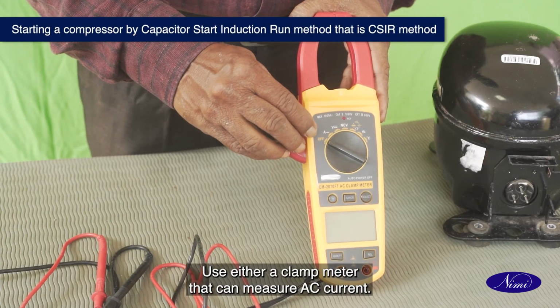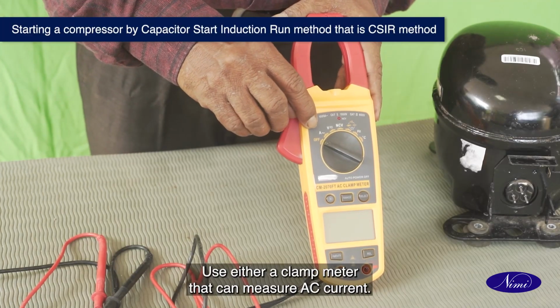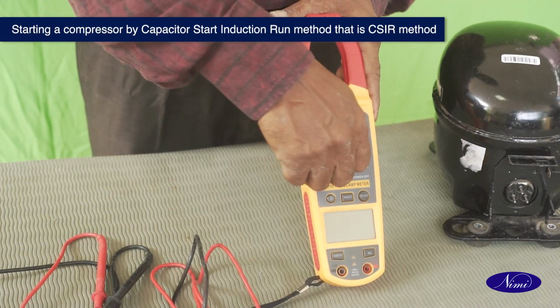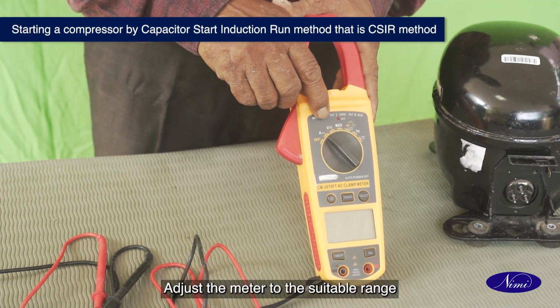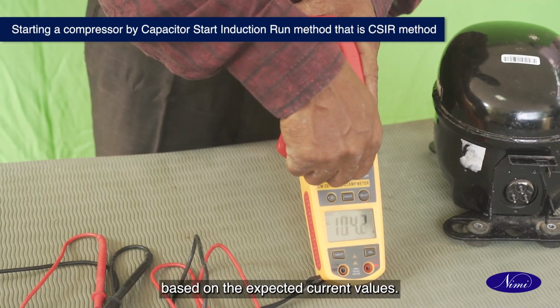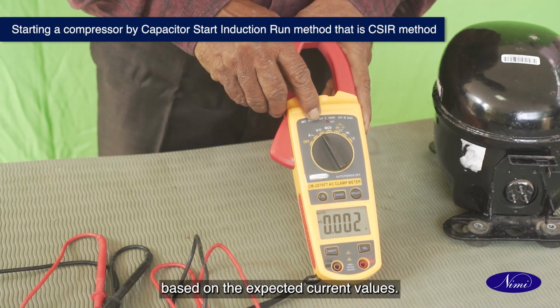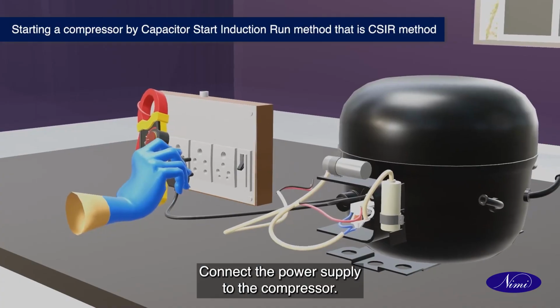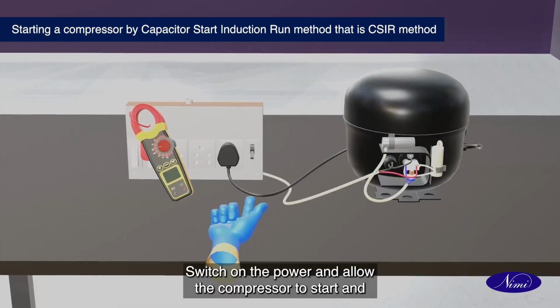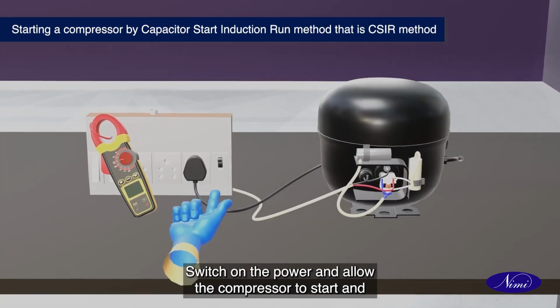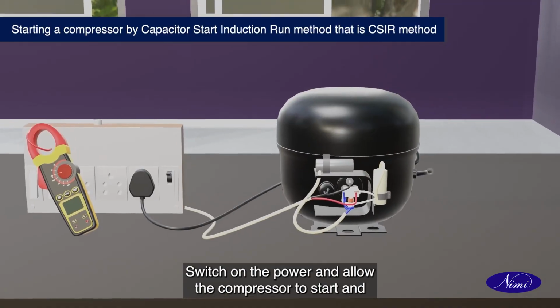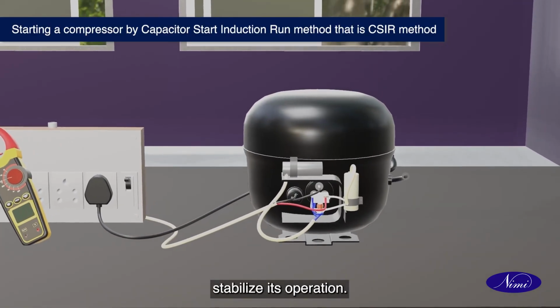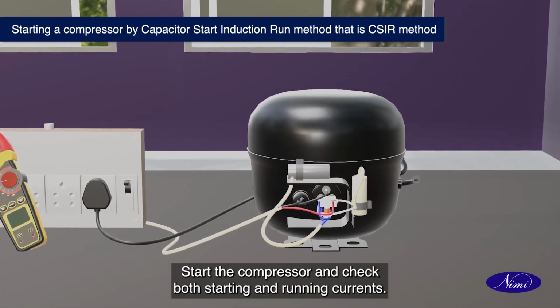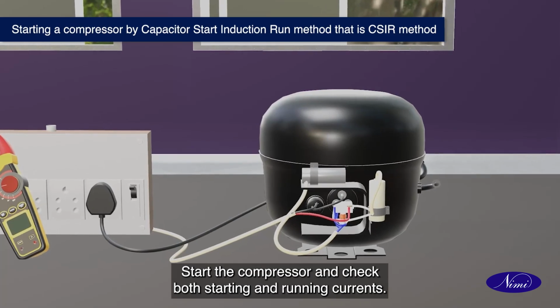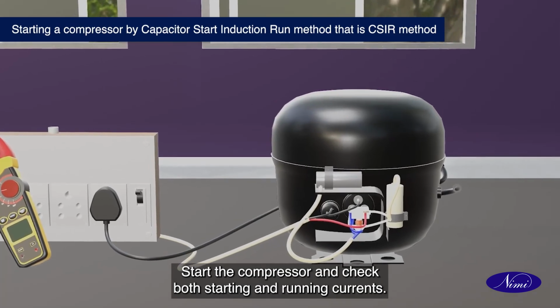Use a clamp meter that can measure AC current. Adjust the meter to the suitable range based on the expected current values. Connect the power supply to the compressor. Switch on the power and allow the compressor to start and stabilize its operation. Start the compressor and check both starting and running currents.